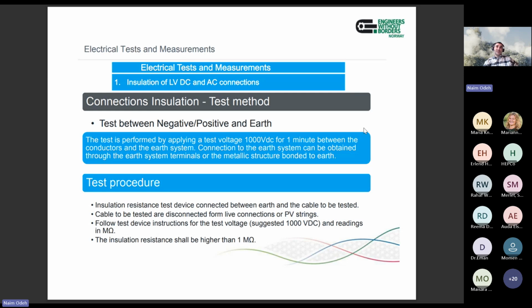So you do the insulation test by using the Megger, for plus and minus with earth. You apply 1000 volt DC. If you are familiar with using a Megger, you apply it for 1 minute and then check the result. The result will be in megaohm. You can say that the insulation reading is like an indication of resistivity.